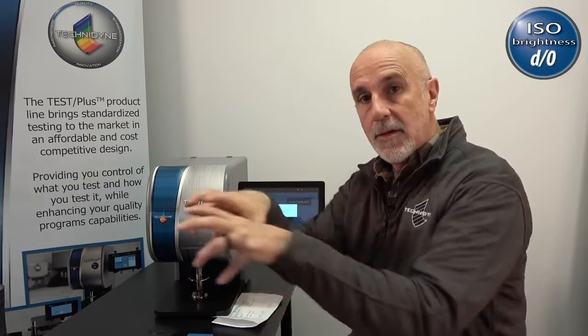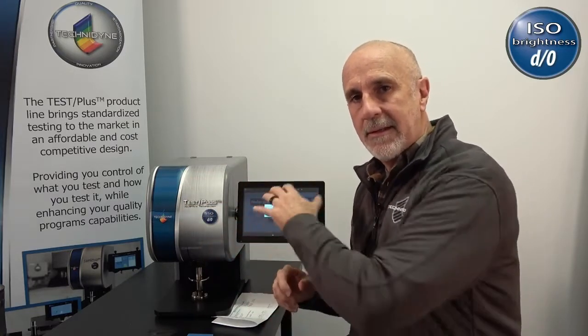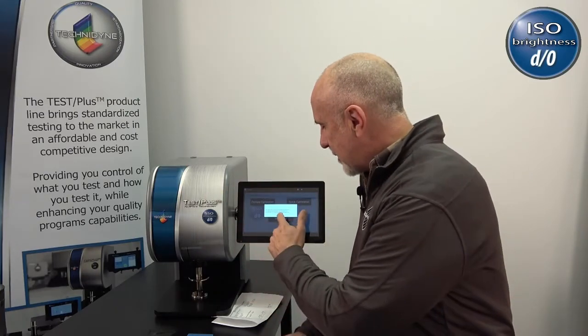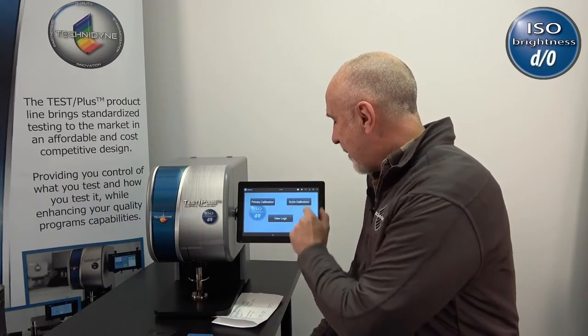And now that the instrument's in a good state of calibration, it's going to evaluate the working standard, and store the value for that standard in the software so that when you do the quick calibration, it's going to retrieve that value. Okay. So when that's done, I select OK. The primary calibration is complete. I can navigate back to the home icon, and I can begin my testing sequence.